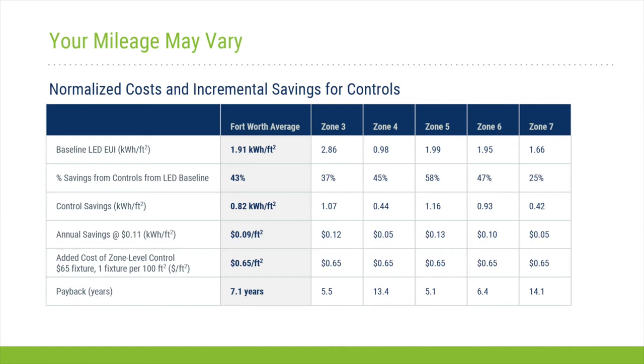So there are some T-LEDs out there now that have a wireless capability, so that way I could walk around with a local device such as a smartphone where I could quickly tune them directly, but those are less common. Most T-LEDs are static output, meaning whatever the rating on the box is, that's how much they put out. So no, to answer your question, virtually no T-LEDs offer the ability of high-end trim. There are some T-LEDs that dim, but again, if your fixture didn't already have that dimming capability, you don't have that at all.